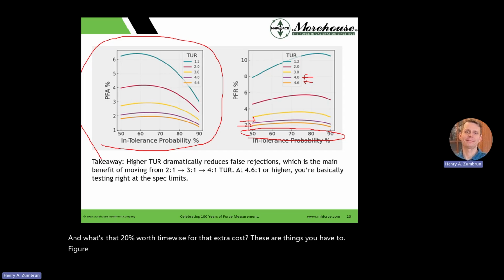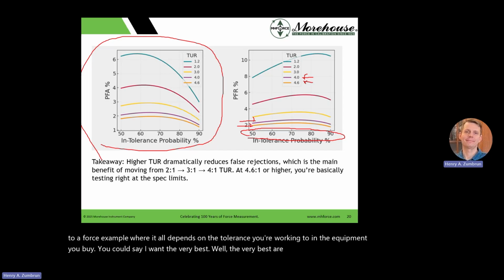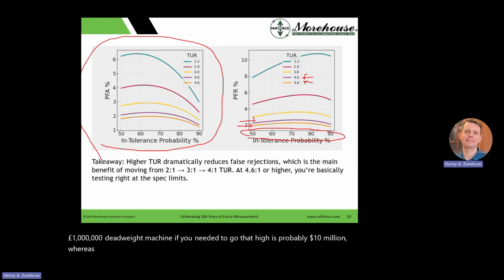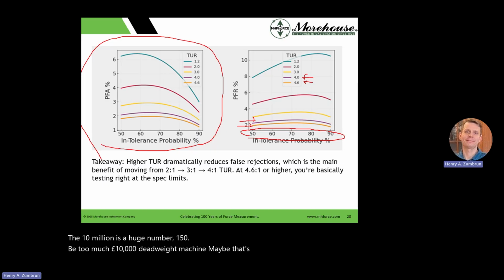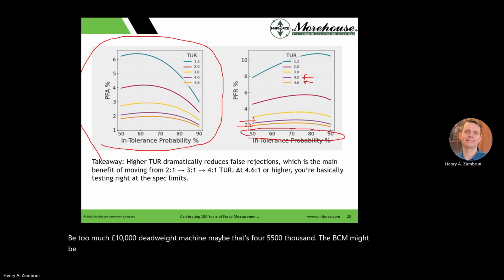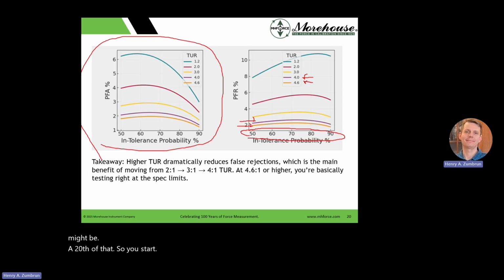I started with a resistance example of resistors in batch manufacturing and went to a force example, where it all depends on the tolerance you're working to and the equipment you buy. You could say, I want the very best. Well, the very best are dead weight machines. A 1,000,000-pound dead weight machine, if you needed to go that high, is probably $10 million, whereas a 1,000-pound dead weight machine, a lot less money than that, is probably $150,000, right? The 10 million is a huge number. 150 might be too much. A 10,000-pound dead weight machine, maybe that's 450, 500,000. The BCM might be a 20th of that. So you start looking at these numbers and at the cost of things. You just have to run them all.